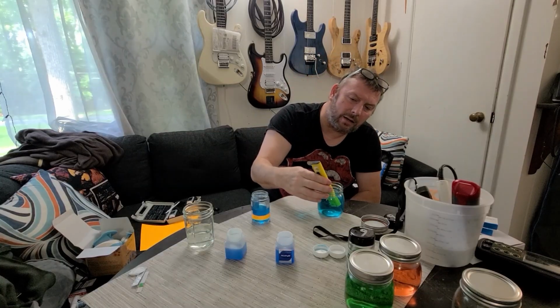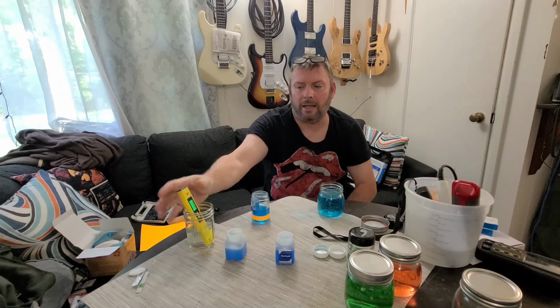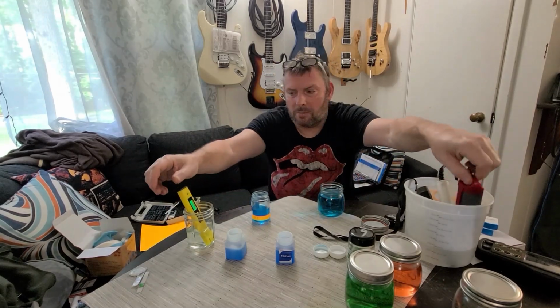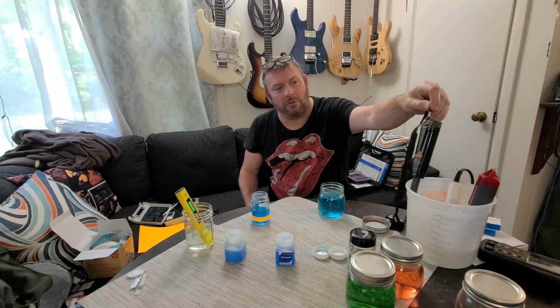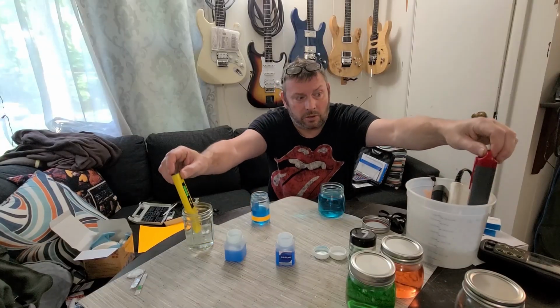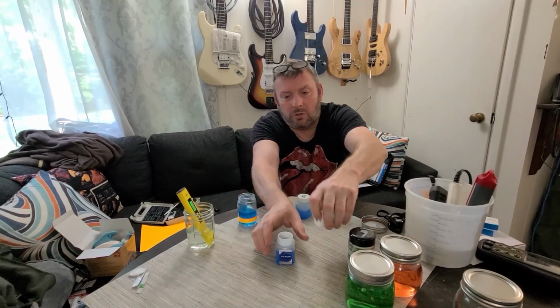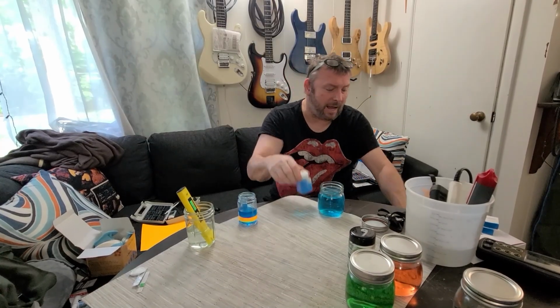So it's high again. Oh, it's almost up to 9.5. So once again, it's high. So our two cheapy meters are typically high on the pH side by about a third of a point, 0.3, give or take a little bit there. Our AC Infinity tends to be a little bit high, off by 0.2. So 0.2 out of 1 is a fifth. So this AC Infinity is about a fifth of a point off. These are a third of a point off. Hanna, if it is off, it's not more than a fifth, but it's usually spot on, and I guess it depends on the solution. So there you have it. This is what I suspected all along. Hanna for $250, pretty much where it's at.